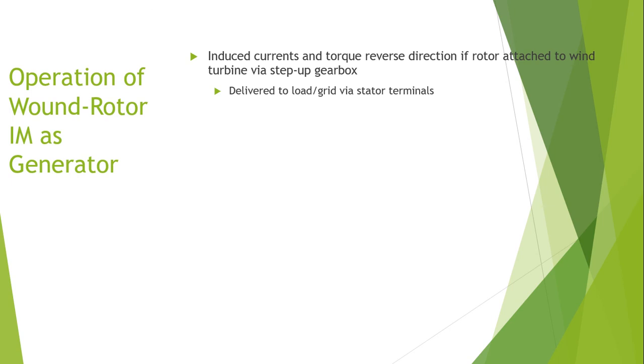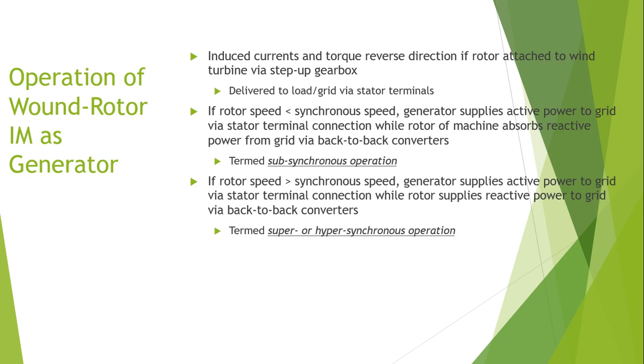Power is delivered to the load via the stator terminal through a step-up gearbox. If the rotor speed is less than the synchronous speed — sub-synchronous operation — the generator supplies active power to the grid via the stator terminal while the rotor absorbs reactive power from the grid via back-to-back converters. If the rotor speed is greater than the synchronous speed — super or hyper-synchronous operation — the generator supplies active power via the stator terminal while the rotor supplies reactive power to the grid via back-to-back converters.